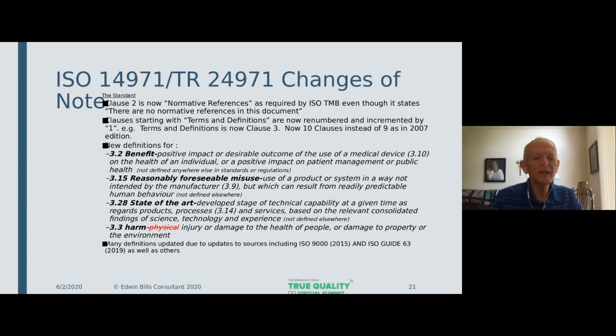And changes of note, now we're going to look at the definitions. We talked about normative references, so we can skip that. There's a new definition for benefit. Nowhere else is the word benefit defined. In the MDR, it's not defined. It's not defined in the FDA's documents. So here's a definition: positive impact or desirable outcome of the use of a medical device on the health of an individual, or positive impact on patient management or public health. And that definition will help you as you're doing benefit-risk analysis.